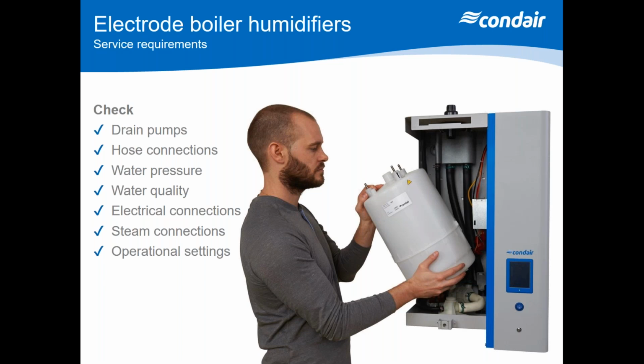Now, in most cases, these humidifiers will have a way of measuring the current draw. And then they will look to detect a current draw over a certain period of time. If it goes out of that period and it can't achieve the correct current draw, it will flag up an alarm. Most of these units will have a common alarm fitted to send a signal back to your BMS. But obviously with cylinders, you need to make sure that you have those available and replace them when they're heavily scaled. Also, the most important thing when you're changing a cylinder is to make sure that the drain pump that dilutes the water in that unit is also checked. Because I've seen so many times where people have taken the cylinders out and forgotten to clean the pump. They put a brand new cylinder back in and find that the cylinder gets wasted or damaged very quickly after fitting. So it's very important to check the pump and clean it.